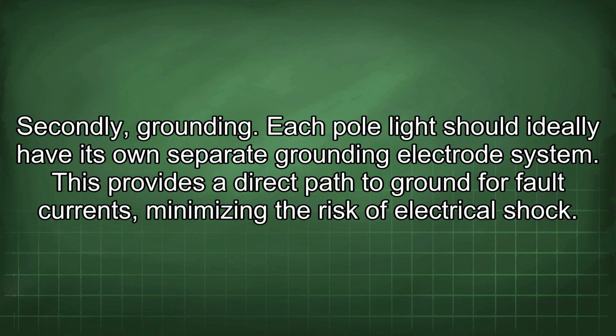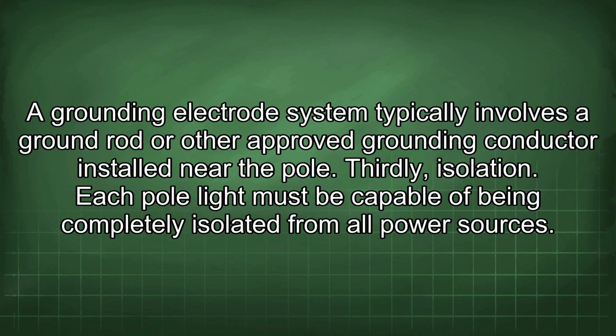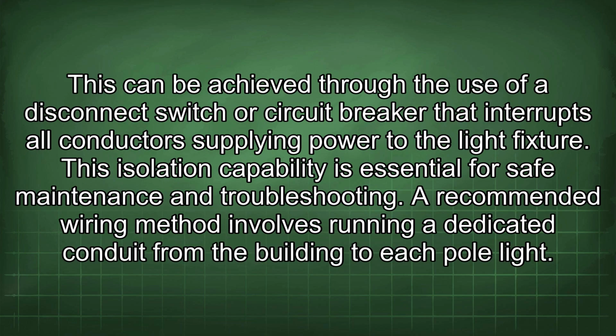Secondly, grounding. Each pole light should ideally have its own separate grounding electrode system. This provides a direct path to ground for fault currents, minimizing the risk of electrical shock. A grounding electrode system typically involves a ground rod or other approved grounding conductor installed near the pole. Thirdly, isolation. Each pole light must be capable of being completely isolated from all power sources. This can be achieved through the use of a disconnect switch or circuit breaker that interrupts all conductors supplying power to the light fixture. This isolation capability is essential for safe maintenance and troubleshooting.